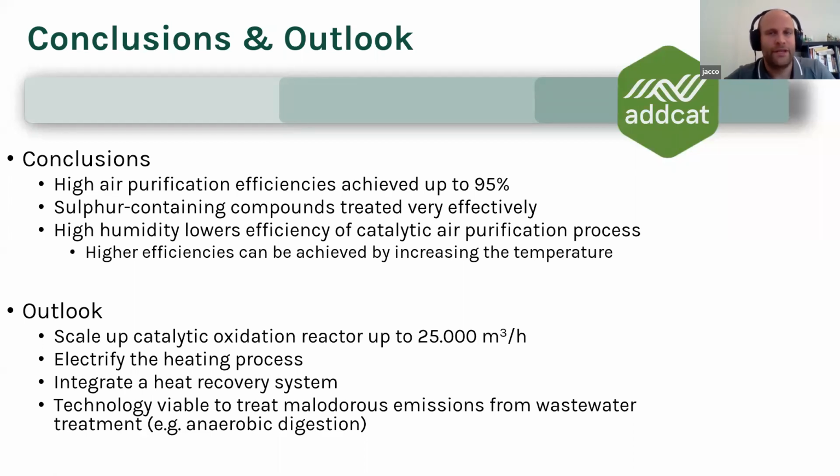But this can be simply remedied just by increasing the temperature a bit, because there's a competition between water vapor and the contaminants for adsorption onto the surface of the catalyst. The outlook is that we are currently scaling up catalytic oxidation technologies to larger volumetric flow rates, electrifying the heating process, and also integrating a heat recovery system.